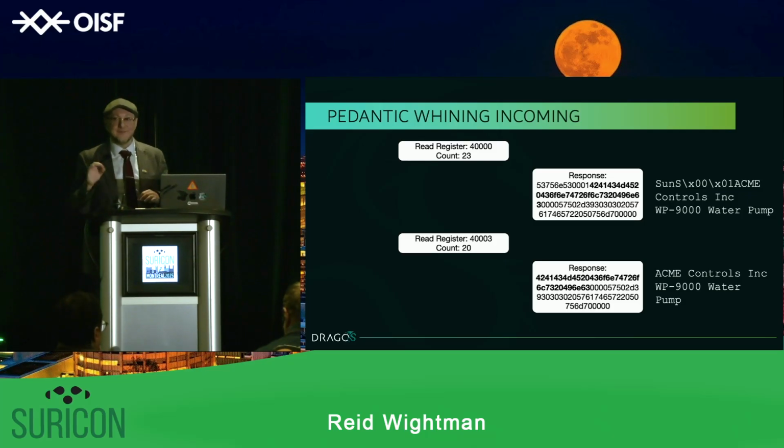And there's another little wrinkle to Modbus too, which is that there's an infinite number of ways to request the same data. In this case, this is using that SunSpec Modbus overlay. You can read the device identifier a lot of different ways. So you can say read register 40,000 and read 60 bytes of data or whatever, and you'll get back a payload that contains the SunSpec Modbus header, and then the data table identifier 1, and then the manufacturer of the equipment.